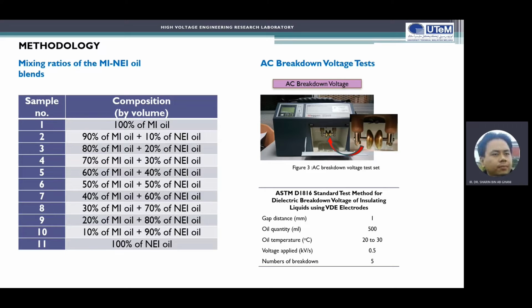This is the mixing ratios of the mineral insulating oil and natural ester oil blends. We produce 11 samples, where sample 1 is 100% mineral insulating oil, and sample 11 is 100% NEI oil. Samples 2 until 10 are variations of the composition between mineral and natural ester oil, from the highest mineral oil to the highest natural ester oil. At the right side is the AC breakdown voltage test using Megger OTS 60PB in our lab, so that we comply with the standard ASTM D1816.